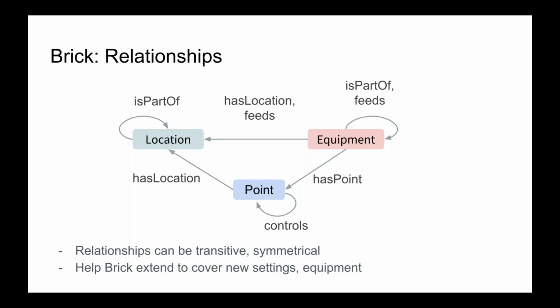Relations can be transitive: if A is contained within B and B is contained within C, then A can be considered contained within C. Things can be symmetrical, and we can add whatever properties we want to these relationships. What relationships do is allow Brick to extend to cover new settings and new equipment. Whether I have an air-based HVAC system or a radiant system, there is still a notion of sequence. An air handling unit will have a feeds relationship to my VAV the same way a part of my radiant system would be upstream of another part. These relationships are able to port across various scenarios.